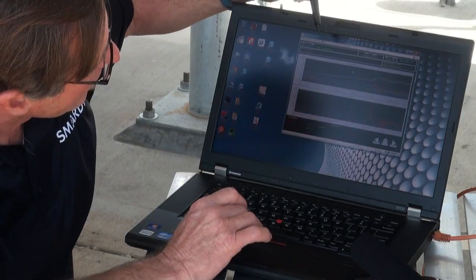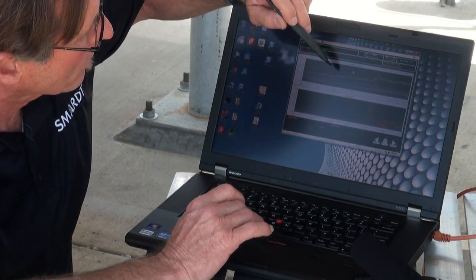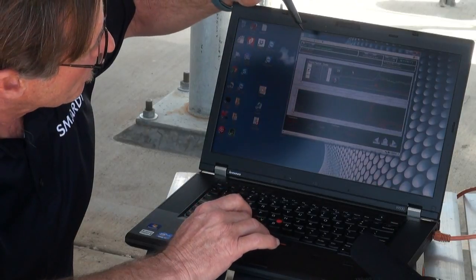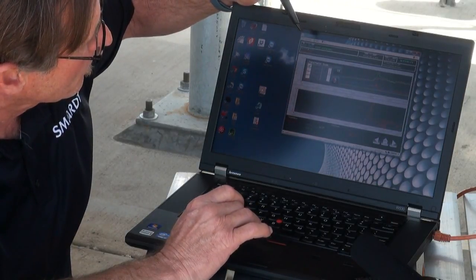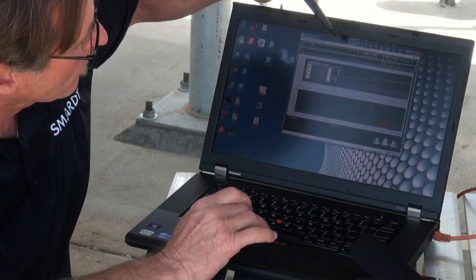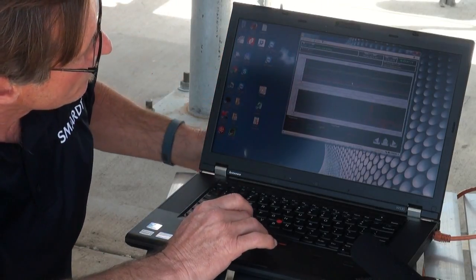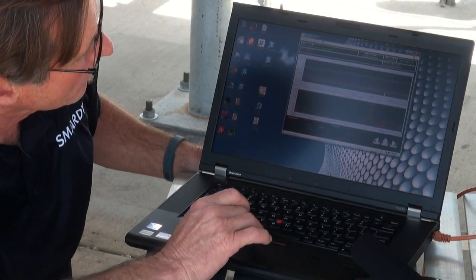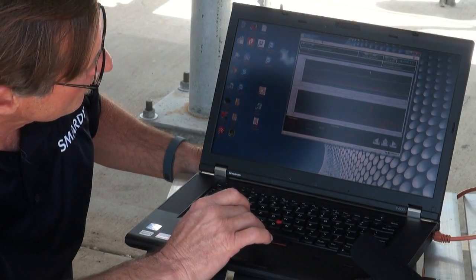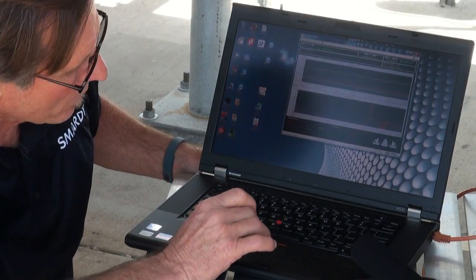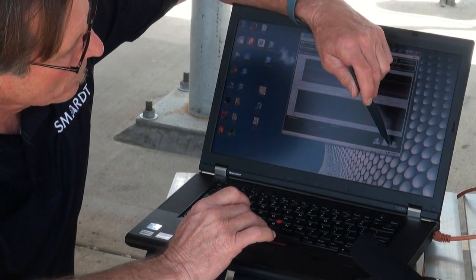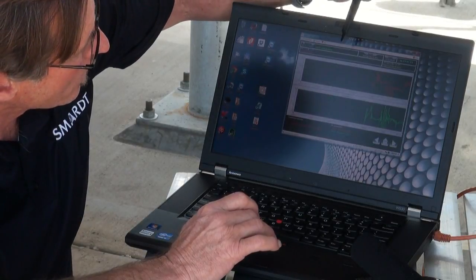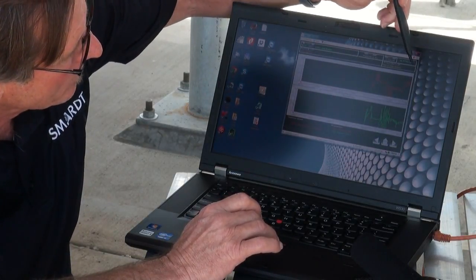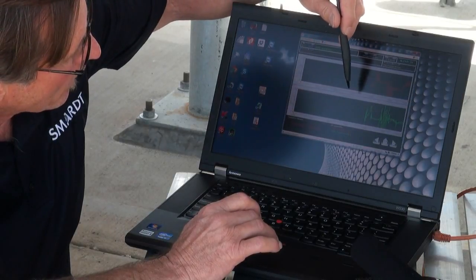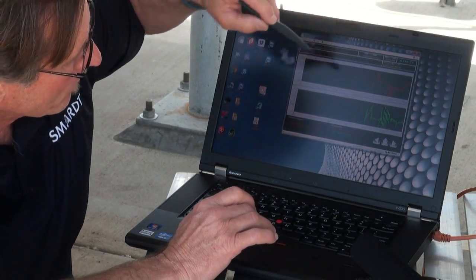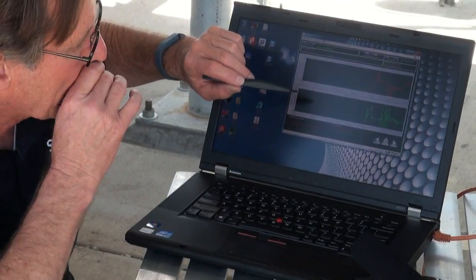Right now it's set for a scale of 6 hours. You can double tap that and set it for 1 hour, and hit OK. So you can get an hour, what it's been doing for the hour. You can go to one of these side arrows. And the same for compressor demand, same for the PID output. That's on the expansion valve.